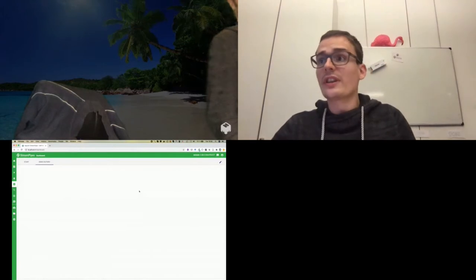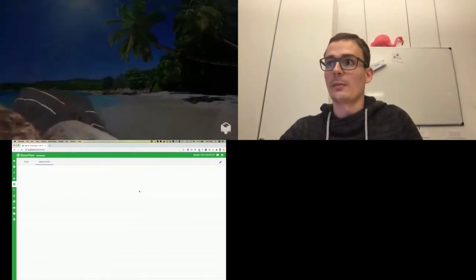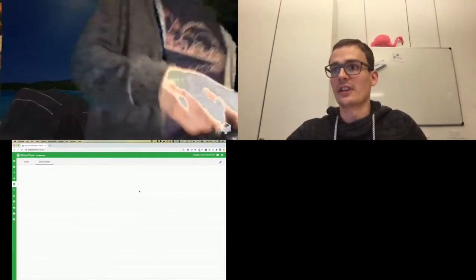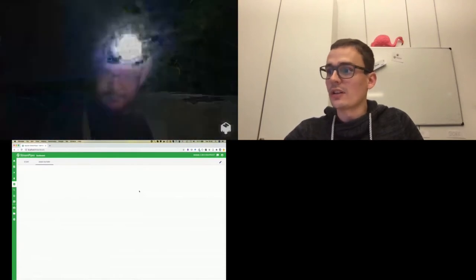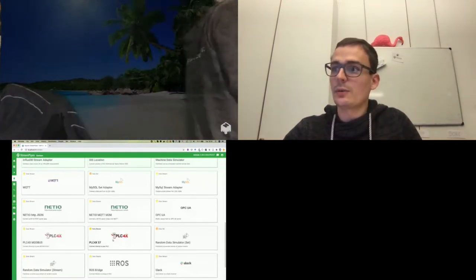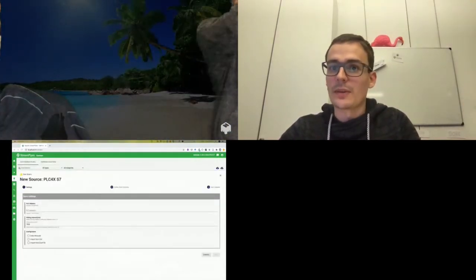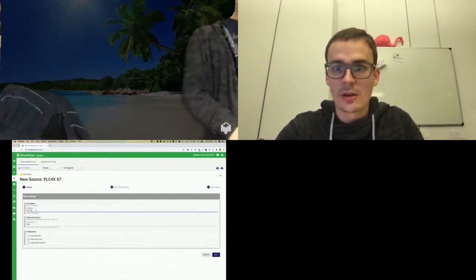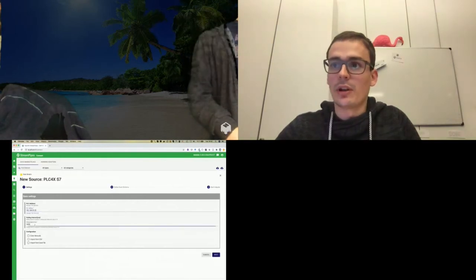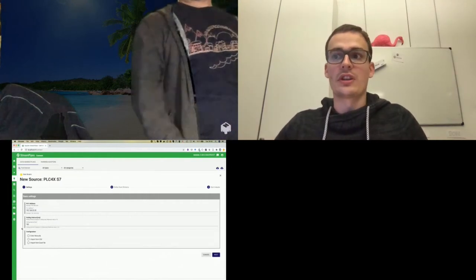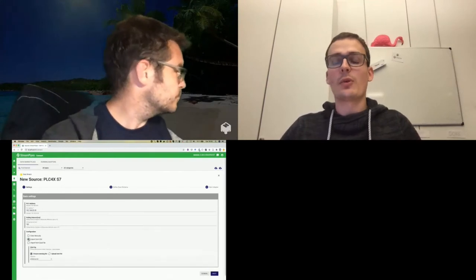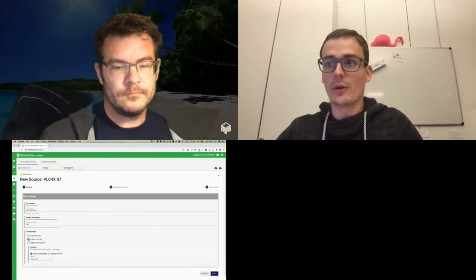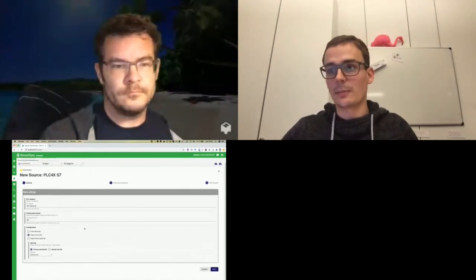And in the first step, we want to connect our PLC. So therefore, we have StreamPipes Connect. And here we have those different adapters. And if I scroll down, you will also see a specific adapter for PLC4x. So we can select this one. Then we have to provide the IP address of the PLC and also the polling interval. And we have to define which registers we want to read. So we can do this manually by entering the registers. But we can also export a CSV or Excel file from the TIA portal and directly import it into StreamPipes. So you don't have to manually configure the adapter.